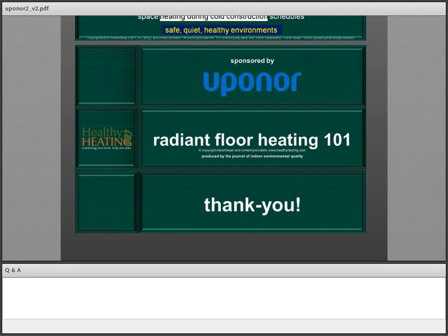Now, how most systems work with proper controls is you have what we call a weather compensator, or indoor-outdoor controller, or reset control—three phrases for the same device. Picture it having a hand outside sensing the outdoor temperature, and another hand holding the supply pipe from the boiler going out to the floor. As your one hand feels the temperature drop outside, the brain says we need to see a temperature increase on the inside.